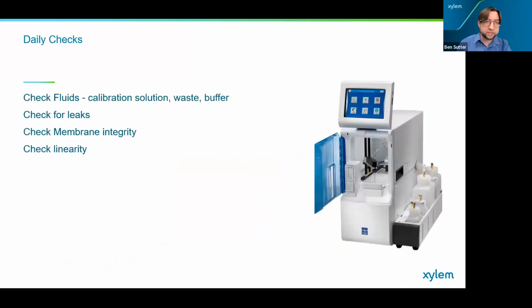The daily checks: you want to check your fluids. Make sure your fluids are topped off, make sure they're fresh, make sure they're not expired. And that should be pretty cursory, should not take much time. Check for leaks. As you run your fluids, make sure that there's no bubbles going in anywhere. Make sure that there's no water or condensation anywhere that you can detect. You can check your membrane integrity and check your linearity.